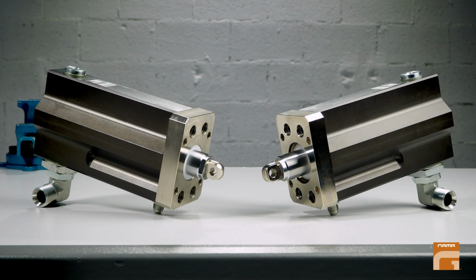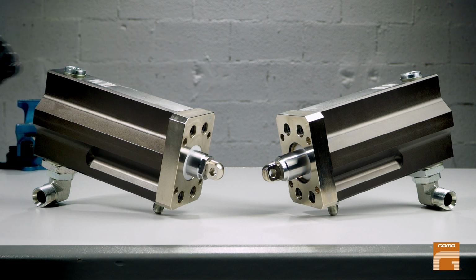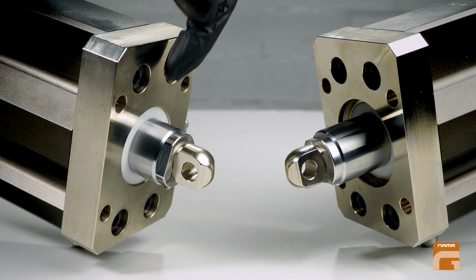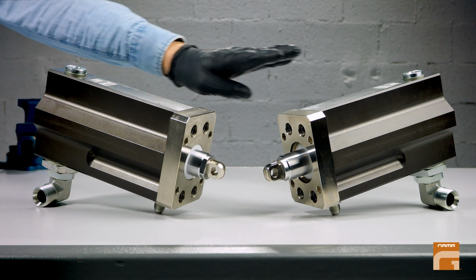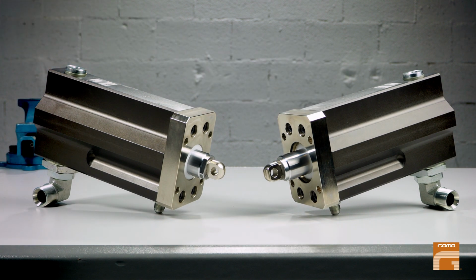We recommend to inspect both ISO and polyol pumps and make a preventive replacement of their seals at least once a year, as these are wearing parts.